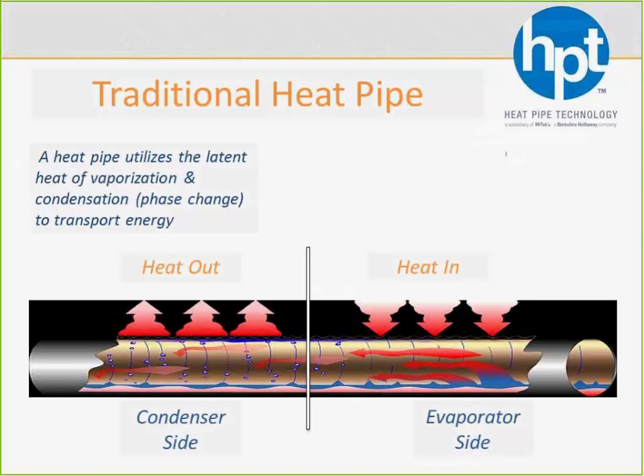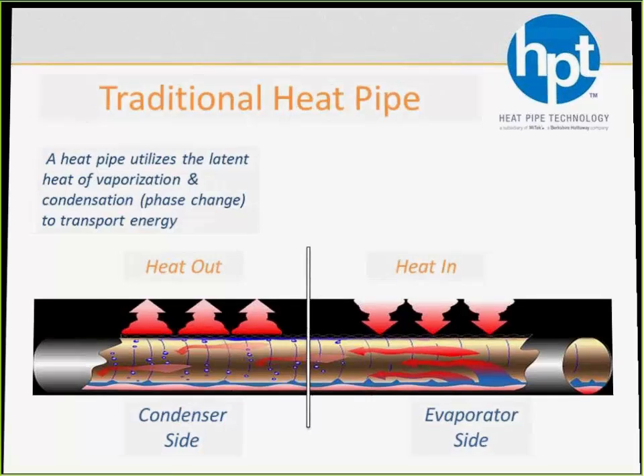Now the heat pipe you're looking at right there is the traditional heat pipe, what we call the single tube type heat pipe, because it's all happening within one tube. You'll find that some of the heat pipes out there use this single tube approach, and because the liquid and vapor go in one larger tube to make that happen, when you see heat pipes using 1-inch aluminum tubes, that's why they're so big. It's because you've got the liquid going this way and the vapor going that way, all inside the same tube.